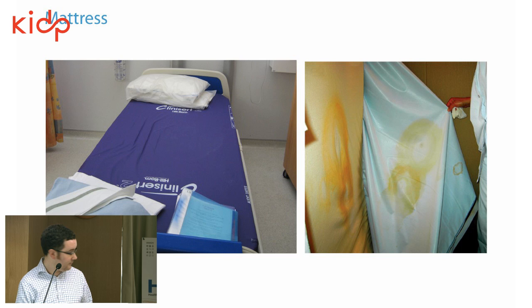So our solution was to look at the mattress itself, specifically the waterproof outer cover. And we put a hydrochromic ink within the waterproof layer. So if the outer layer is pierced and water or fluid gets in, it changes color.